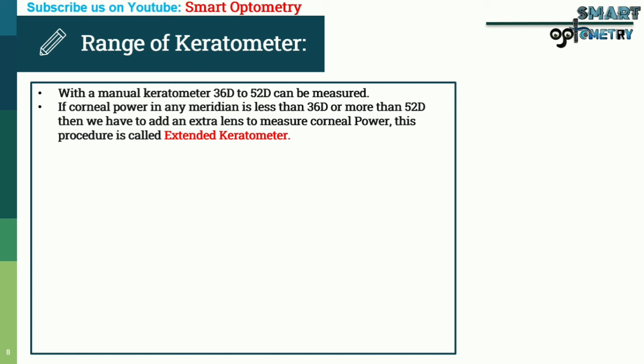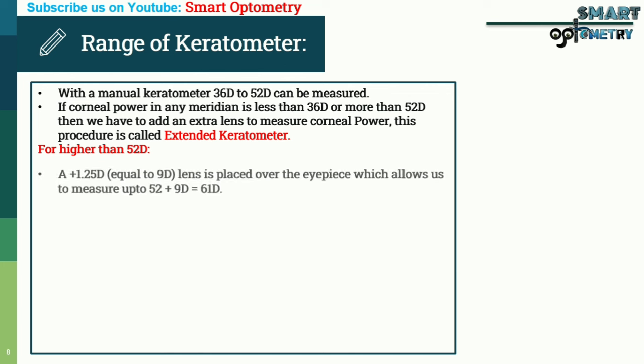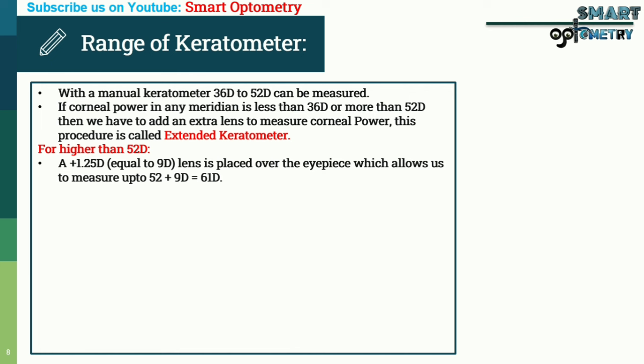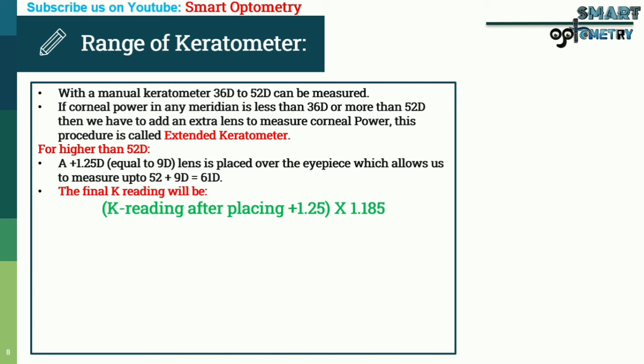For higher than 52 diopters, a +1.25 diopter lens (equal to 9 diopters) is placed over the eyepiece, allowing measurement up to 52 + 9 = 61 diopters. However, the reading obtained after placing the +1.25 diopter lens is not the actual corneal dioptric power. We need to modify this reading using the formula: keratometer reading × 1.185. For example, if the reading with +1.25D is 48 diopters, the final power = 48 × 1.185 = 56.88 diopters.